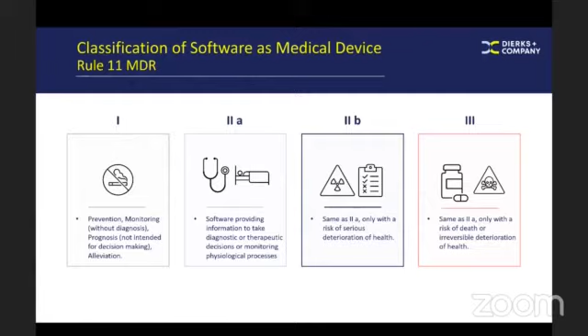How to get the CE mark? You start with the risk classification by yourself, take on the assessment to compile the technical documentation, approach the notified body. The conformity procedure will, in the case of a class 1 product, be executed by the producer himself, however, in all other classes, you need the notified body. And once the notification and the certificate procedure is over, it will have to be informed to the official authority, and then the CE mark can be attached.